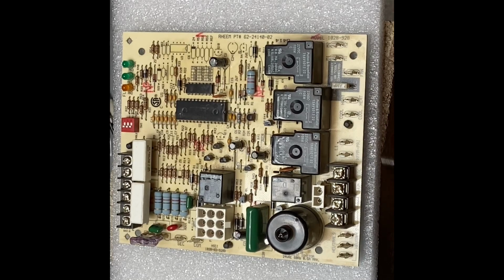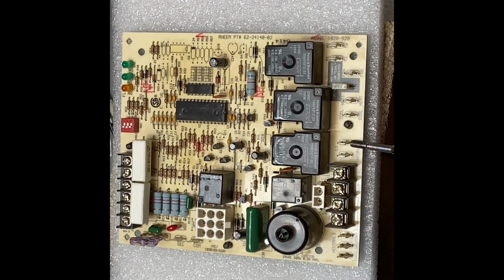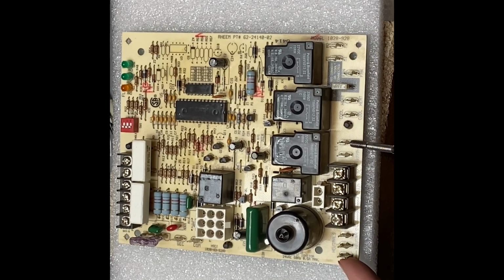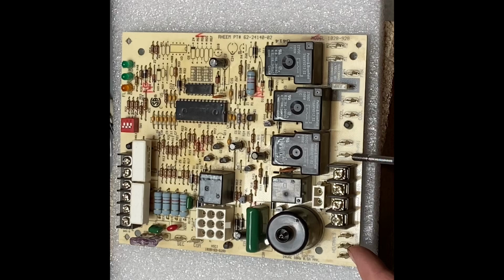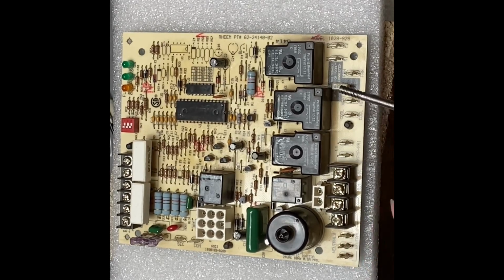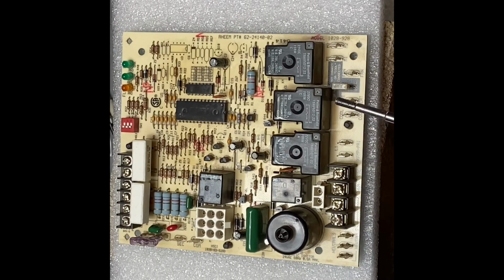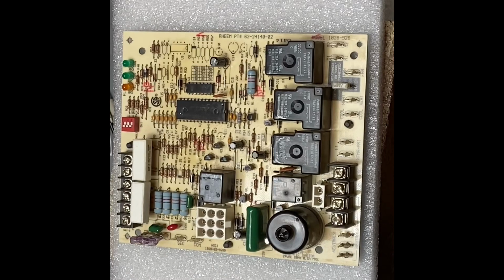So our main power is going to come in through where it says primary and neutral. So this is going to be our 110 volts. Then from there, we can send power to other locations. For example, we have XFMR, so a neutral and a black wire here for primary is going to send 120 volts to our transformer. When you send 120 volts to a transformer, it steps it down to 24 volts. It's going to come back over here to where it says SEC and common. This is going to be our secondary or low voltage side of our transformer.